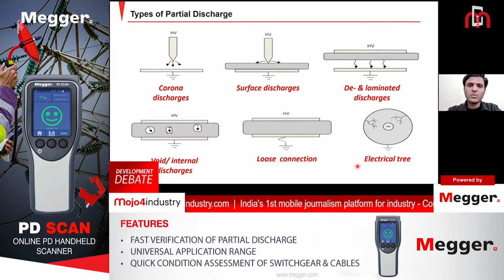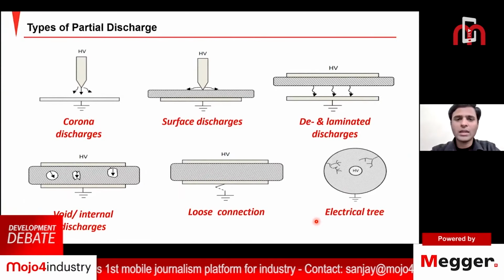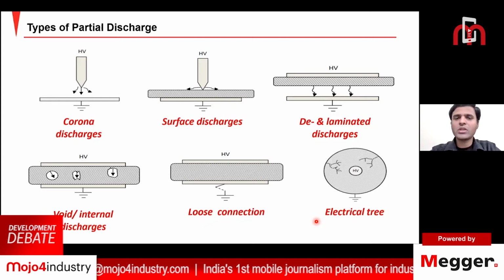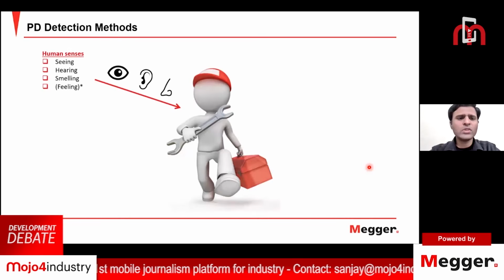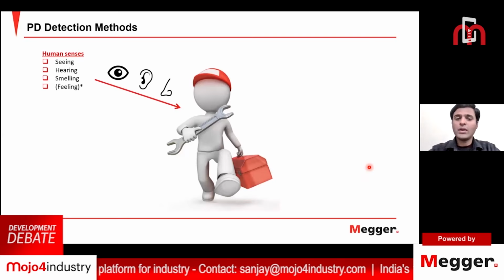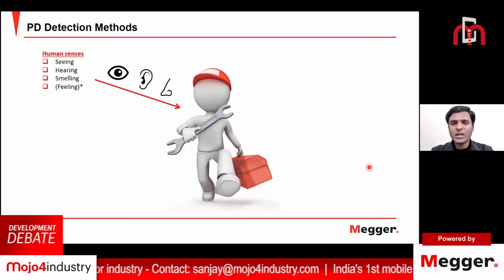And aging means that the life cycle designed for that particular asset gets lessened, and it can get aged and should be replaced before the life cycle it was designed for. However, if we are doing condition based monitoring, we can use particular electrical assets to their maximum life cycle, and also for a longer life period with higher reliability. So we will see how different detection methods are available to detect partial discharges with different characteristics.